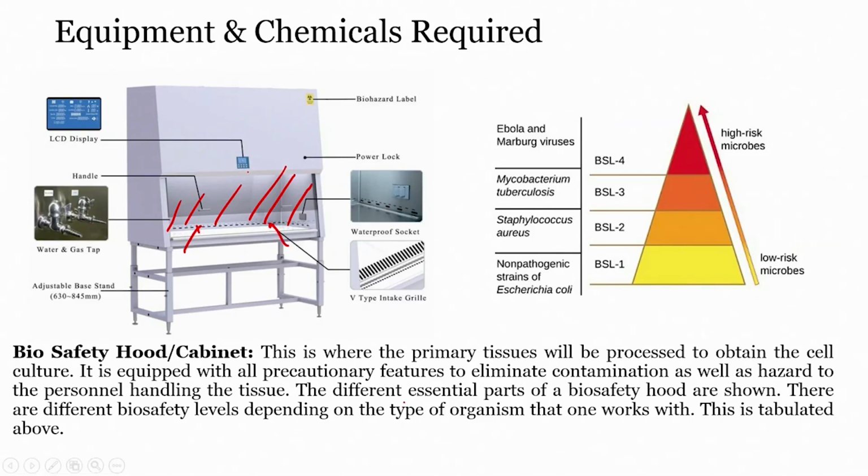It is extremely important to take the precaution of not putting your head within the hood. This equipment is meant for just pushing your hand in and performing your experiment. There is a waterproof socket, and then there is a V type intake grill, which is right over here.